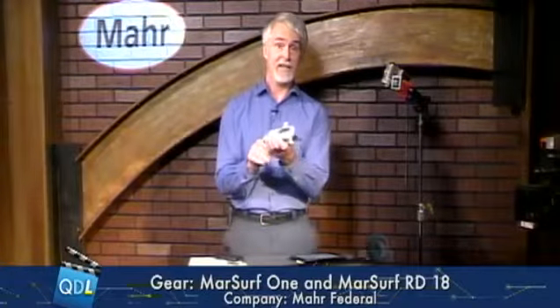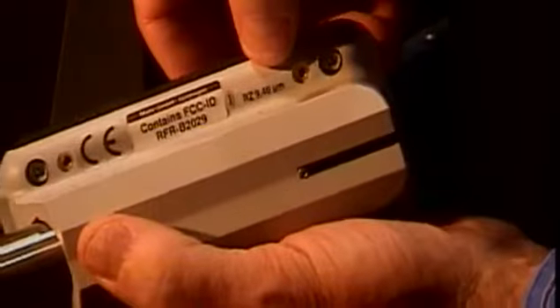Let me show you something. I need to do a calibration on this. I rotate the probe 180 degrees, retract it back inside. I'm ready to do a calibration. Let's go back to the gauge cam here. I click calibrate on the bottom, and it comes up. First thing it asks me is what kind of calibration am I doing? I have my choice of Ra or Rz. I simply look on the bottom of the device, and it tells me we're going to do an Rz measurement, and the reference is 9.46 microns. So I simply come back here, I select Rz, I type in 9.46. It asks me how many passes I want. I'm just going to say one pass just to keep things going. And that's all there is to it.